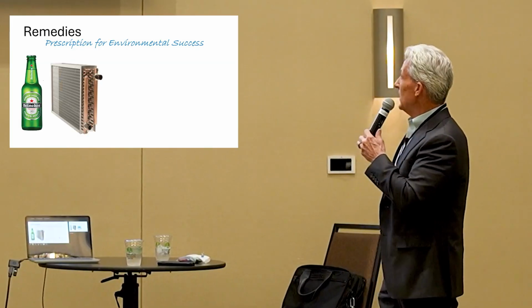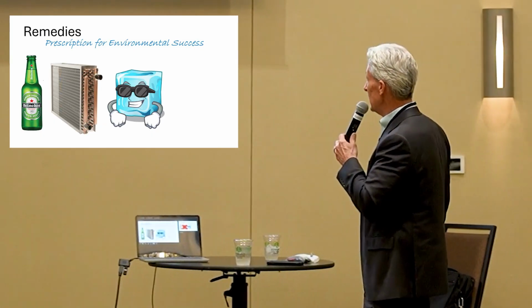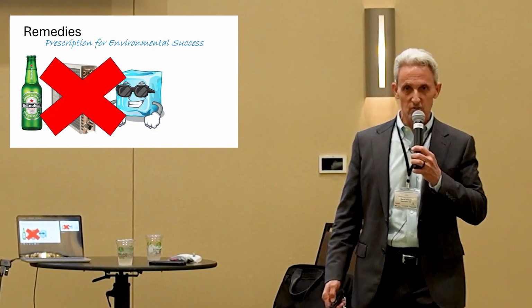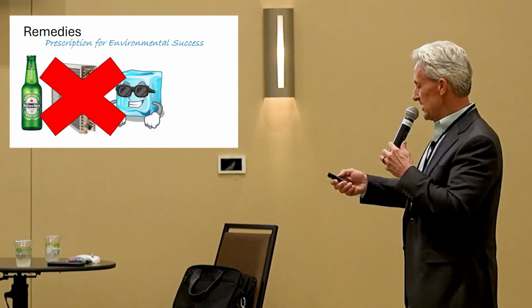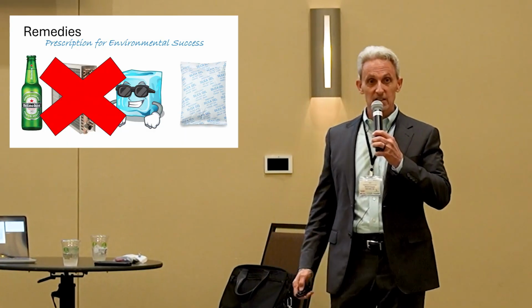So, anytime you have surfaces that are air conditioning and attempting to dehumidify the air at surface temperatures approaching or below 32 degrees Fahrenheit, you cannot use a traditional refrigerant-based system, whether it be chilled water or DX, because you'll freeze the coil. That's it. You're done. In cases like that, you have to use an adsorptive technology such as silica gel. It's the only way to get it done.